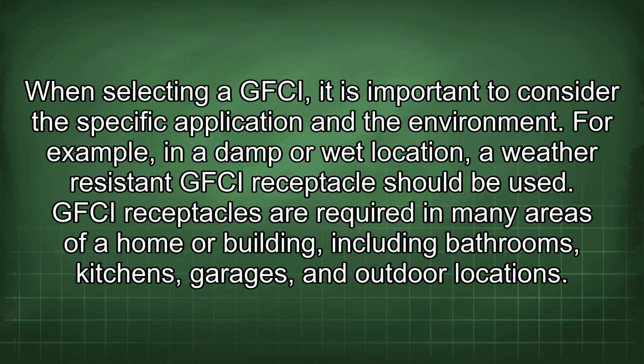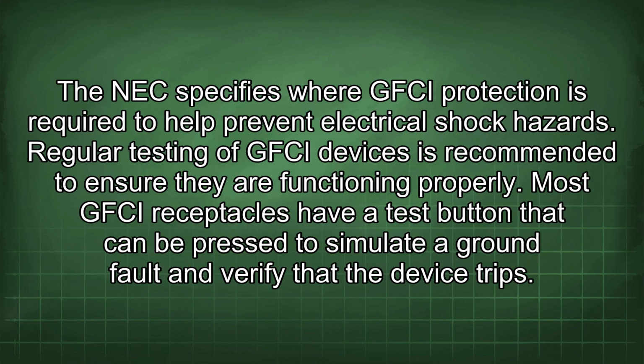For example, in a damp or wet location, a weather-resistant GFCI receptacle should be used. GFCI receptacles are required in many areas of a home or building, including bathrooms, kitchens, garages, and outdoor locations. The NEC specifies where GFCI protection is required to help prevent electrical shock hazards.